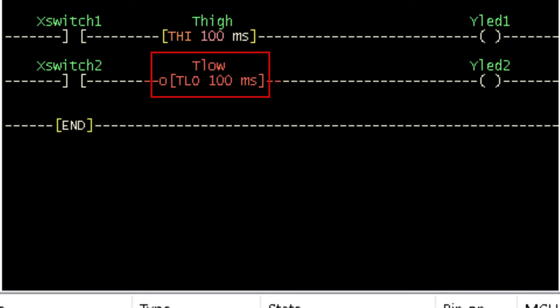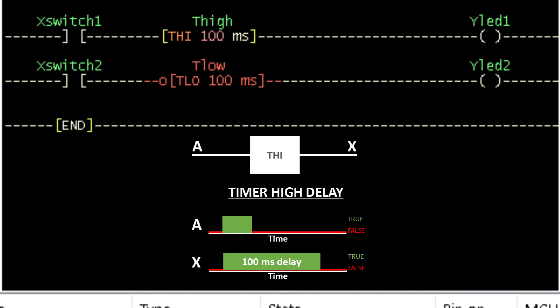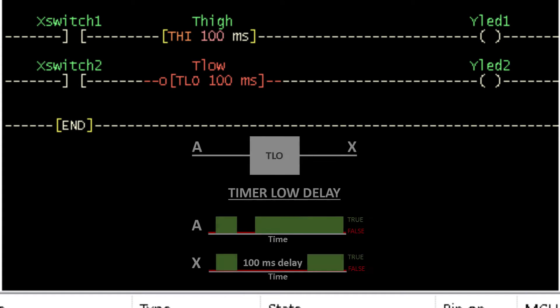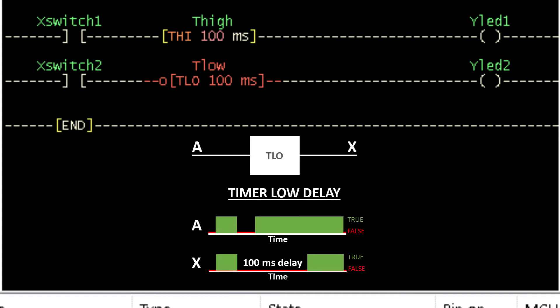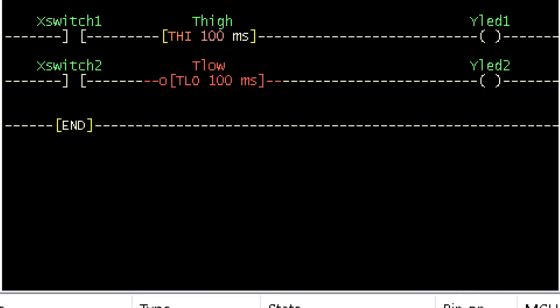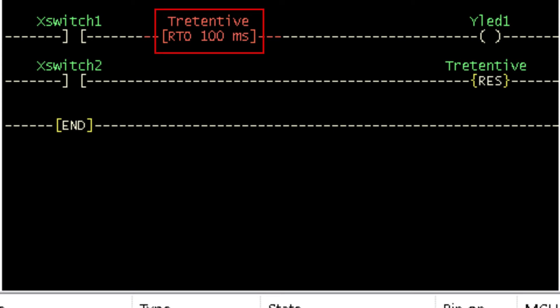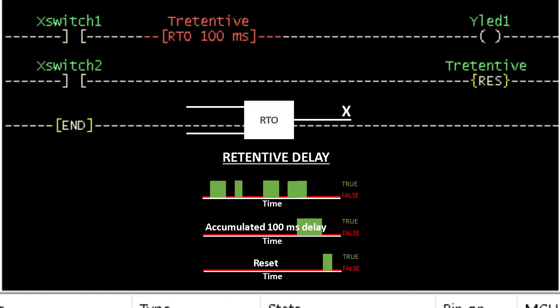The timer high and the timer low are pulse timers. The timer high instruction produces a fixed output pulse when its input goes from false to true, while the timer low operates in reverse — its output goes low for a fixed period when its input goes from true to false. The retentive timer is similar to the turn on delay timer. Unlike the turn on delay timer, the retentive timer does not reset when the input becomes false before the time interval elapses, but rather the input true times are successively added up until the specified time elapses.